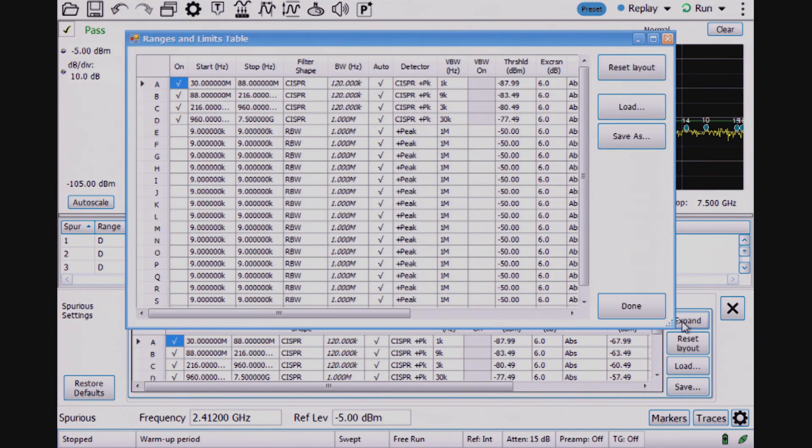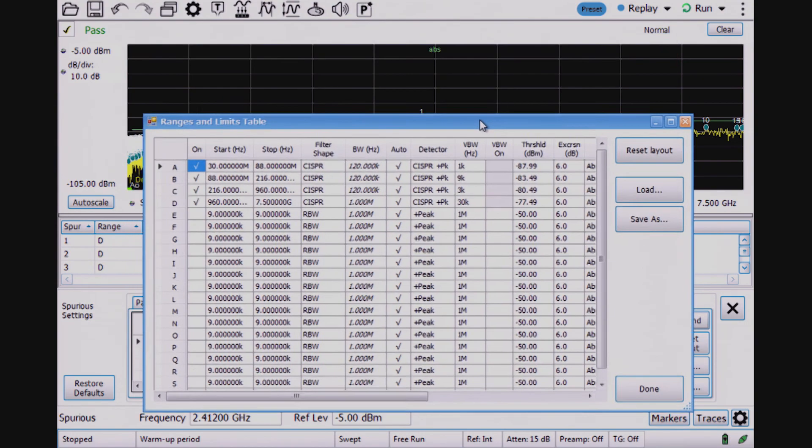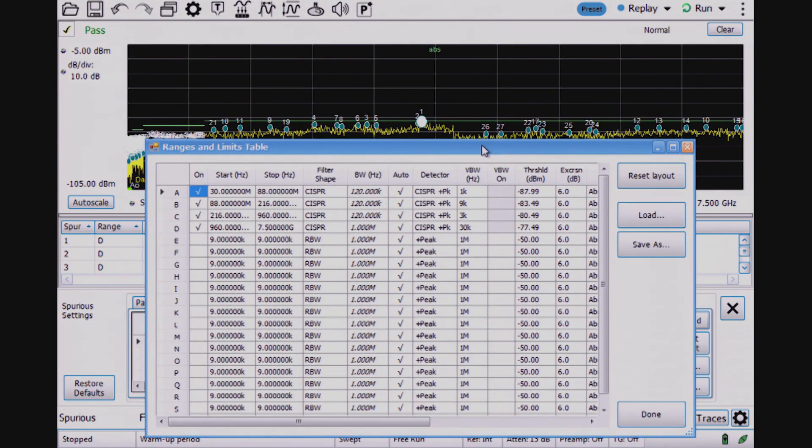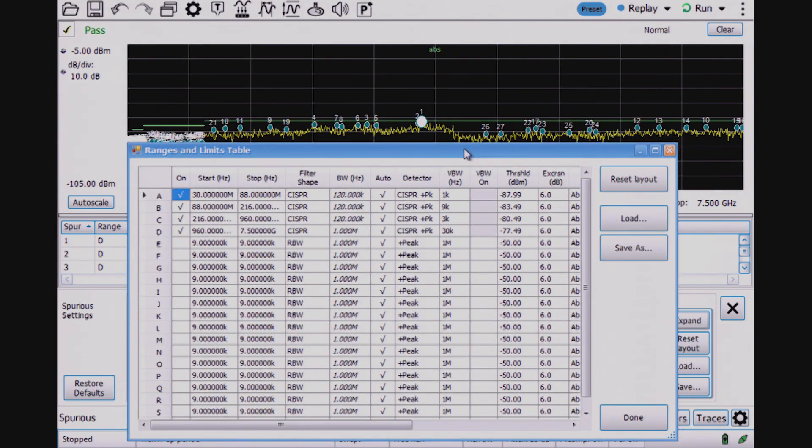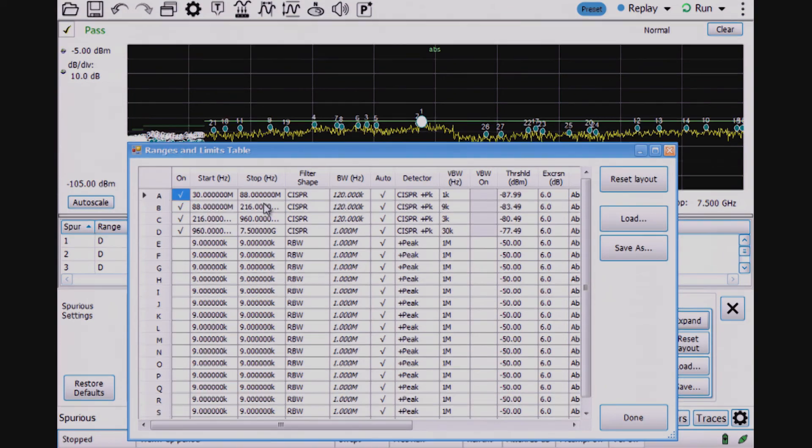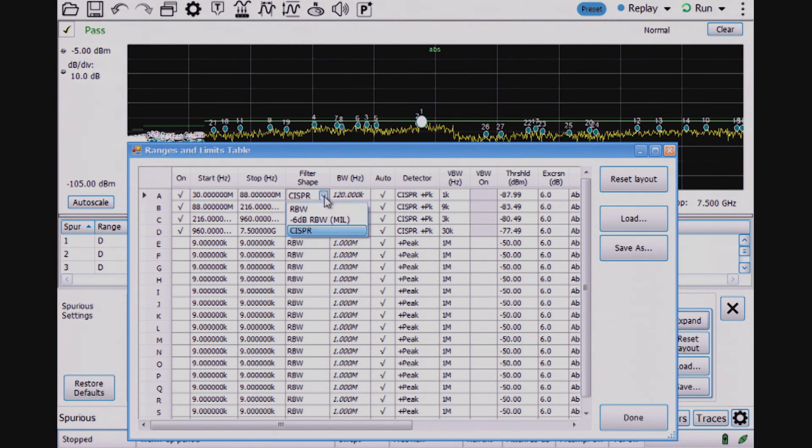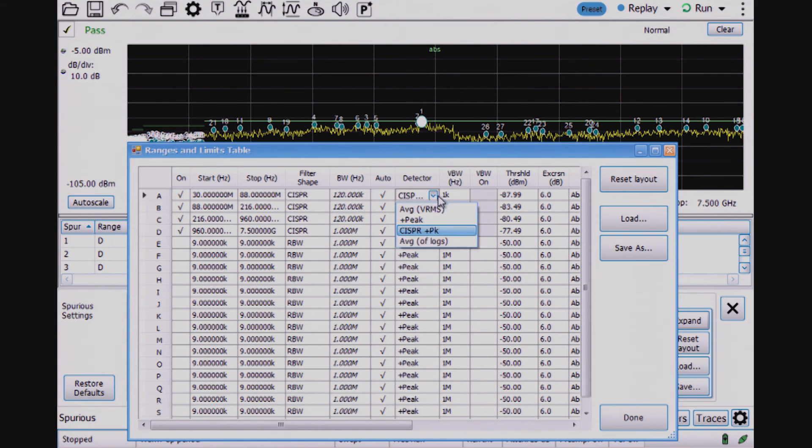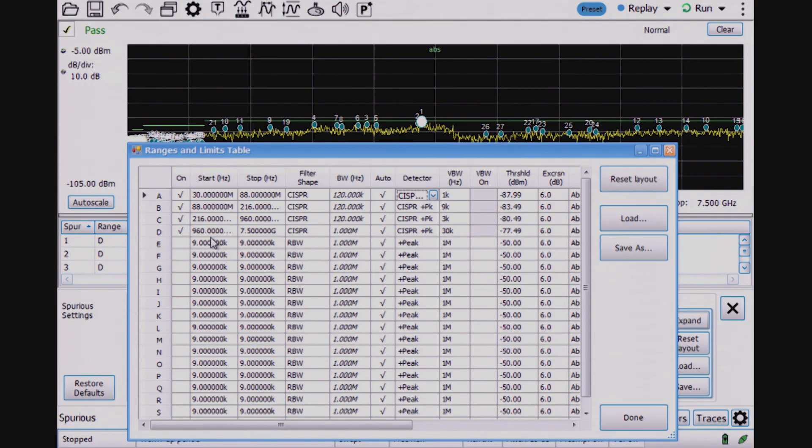I'm looking for all spurs that fall into the definition of the spur that I've set up in this table. Here's the spur table that we can show while this is performing measurements. I'm looking at four different zones, their start and stop frequency. For this EMI pre-compliance test, I'm using a CISPR shape filter with a plus peak detector.